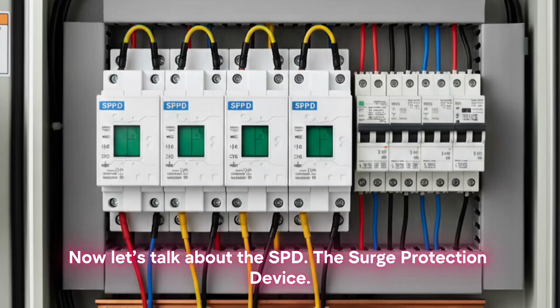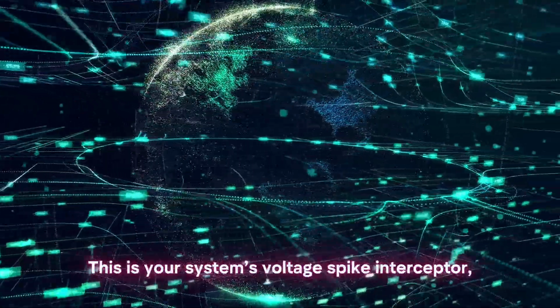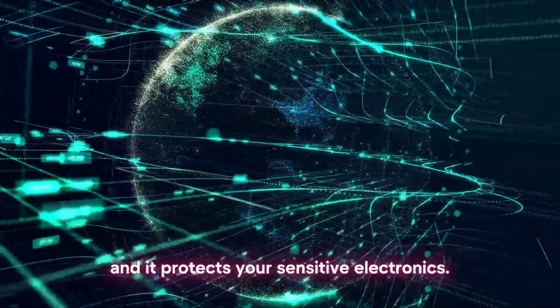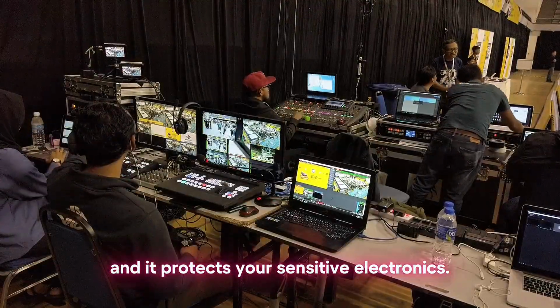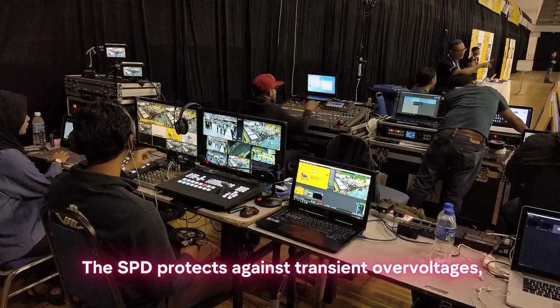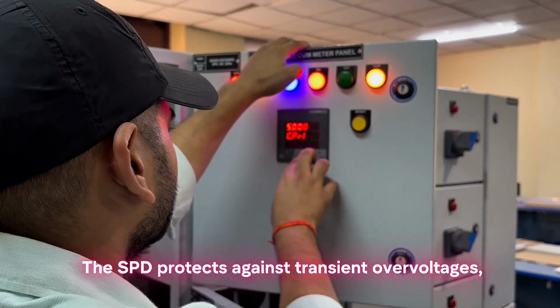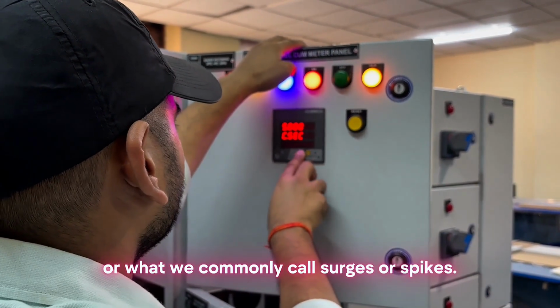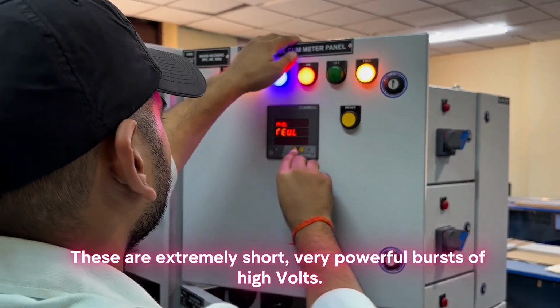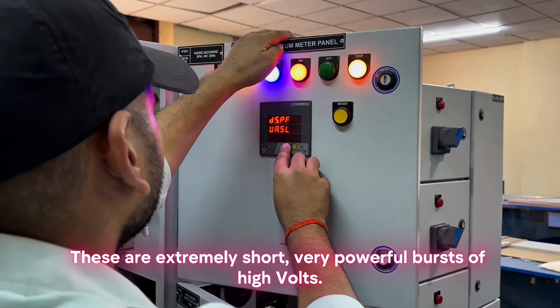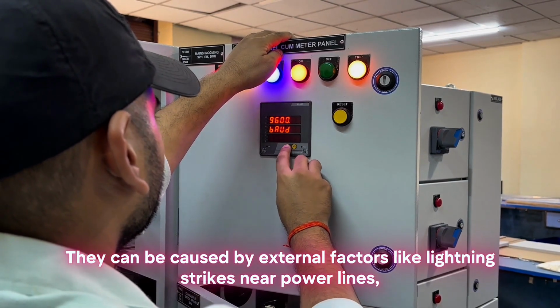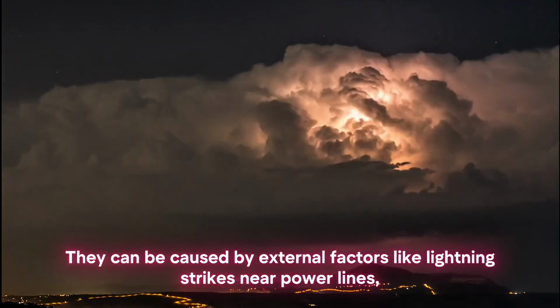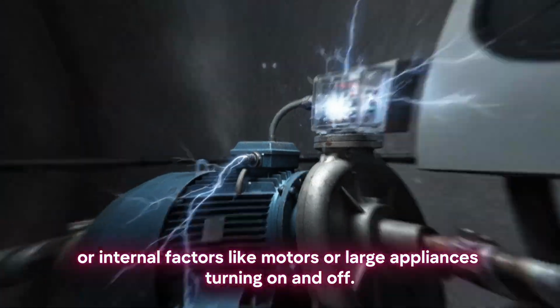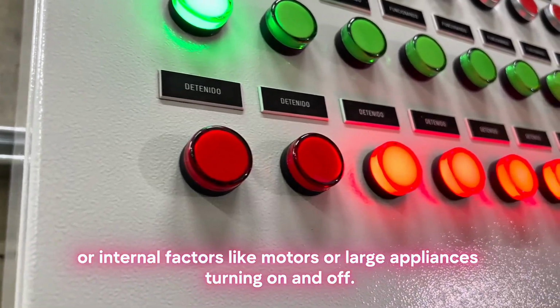Now let's talk about the SPD, the surge protection device. This is your system's voltage spike interceptor, and it protects your sensitive electronics. What it protects against? The SPD protects against transient overvoltages, or what we commonly call surges or spikes. These are extremely short, very powerful bursts of high volts. They can be caused by external factors like lightning strikes near power lines, or internal factors like motors or large appliances turning on and off.